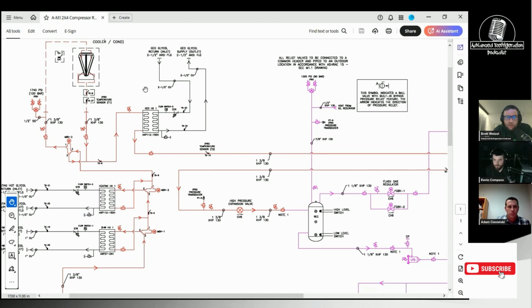Okay. Does that mean you would need to figure that in for what it's running? Basically, would it have to be sized for that worst case scenario, or is the worst case scenario when it's really subcooled at 800 pounds or 600 pounds? So when you said is it sized for, what are you referring to, Brett? The pipe sizes are typically based off of capacity, right? So if you have 1,200 pounds and 60-degree line temperature versus 800 pounds and basically that same temperature.